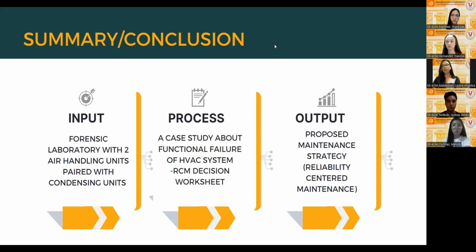So to provide a solution to this, the proponents use the RCM decision worksheet, which aids in assessing the frequency of the necessary maintenance of each HVAC system. So further, the results from the worksheet aided the formulation of the proposed maintenance strategies that must be implemented by the forensic laboratory.